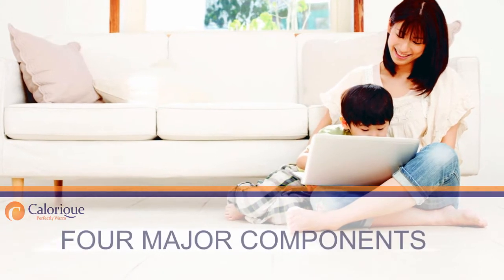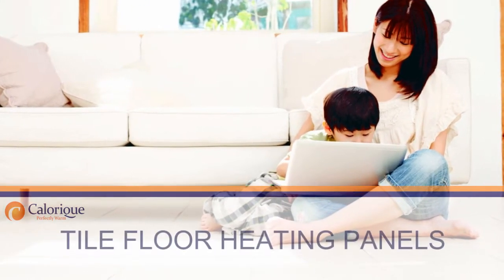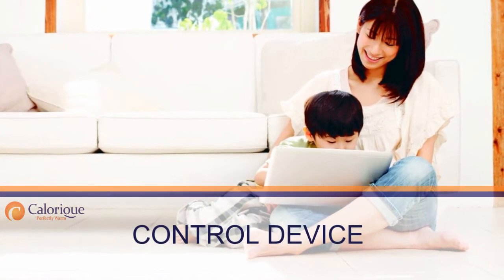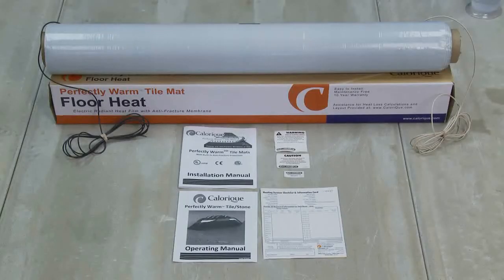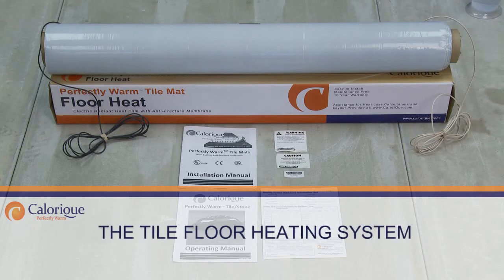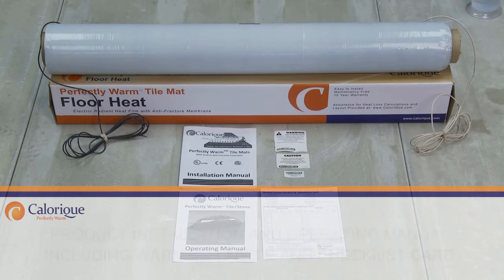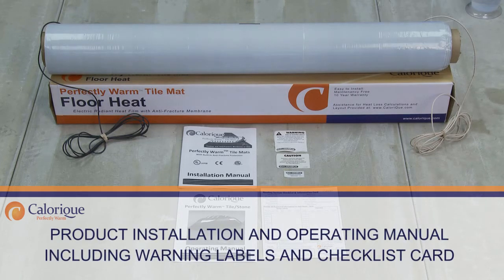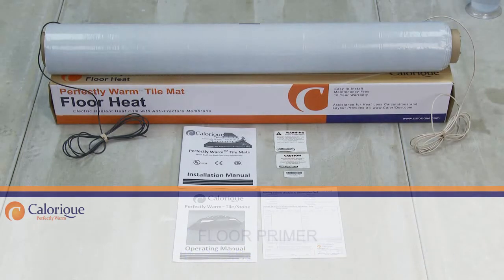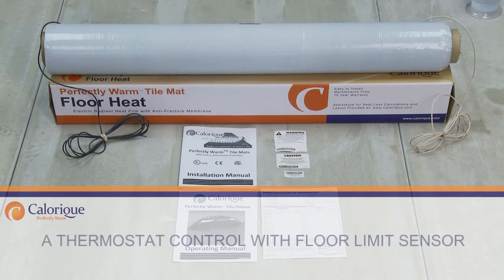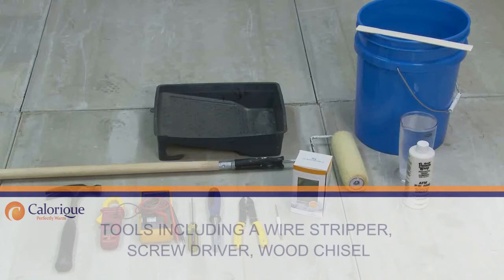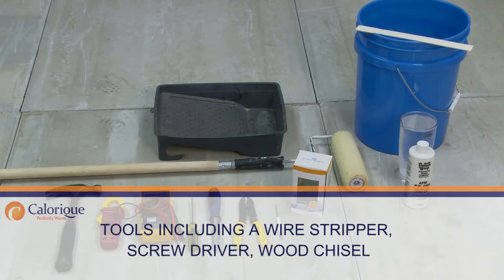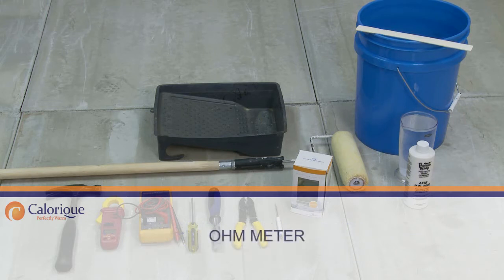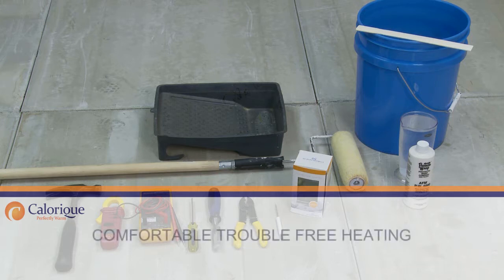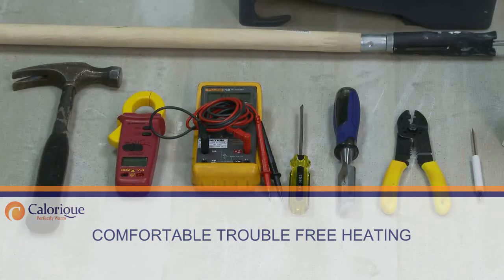The Calorique Perfectly Warm tile heat system is made up of 4 major components: the tile floor heating panels, the wiring, the control device, and the floor structure. You will require the following to complete the installation. 1. The Calorique tile floor heating system and its attached factory connection. 2. The product installation and operating manual, including warning labels and checklist card. 3. A floor primer. 4. A thermostat control with floor limit sensor and junction boxes. 5. Tools including a wire stripper, screwdriver, and wood chisel. 6. An ohm meter.